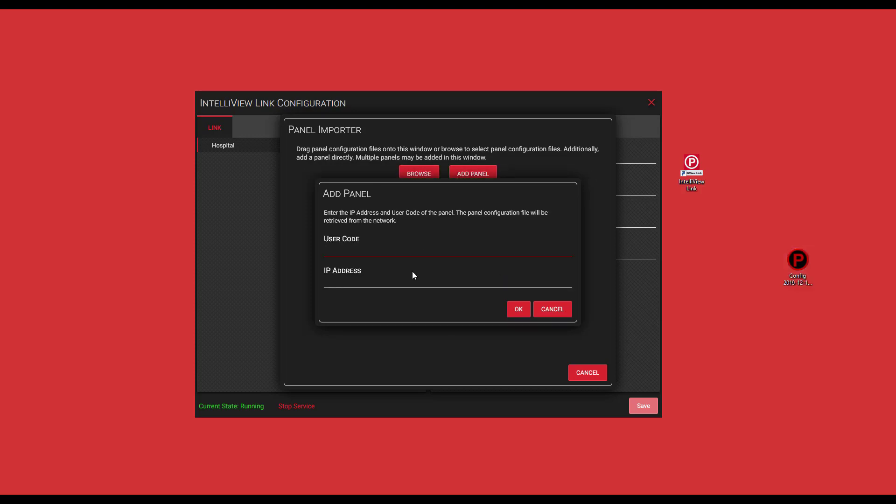The last one here, which is add panel, is going to ask for two pieces of information, the user code and the IP address. This option is normally chosen if the fire alarm control panels are communicating over a network. This option is what we're going to proceed with. So I'll enter my unique user code. Then I will enter my IP address.